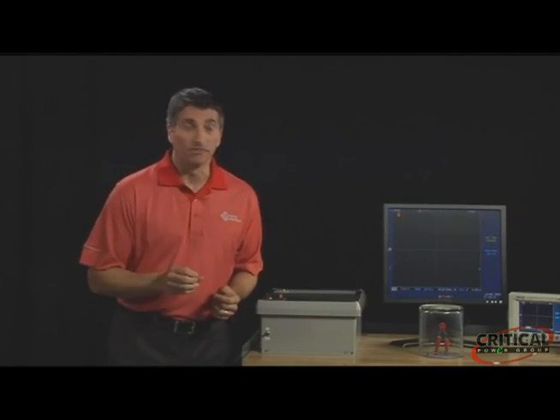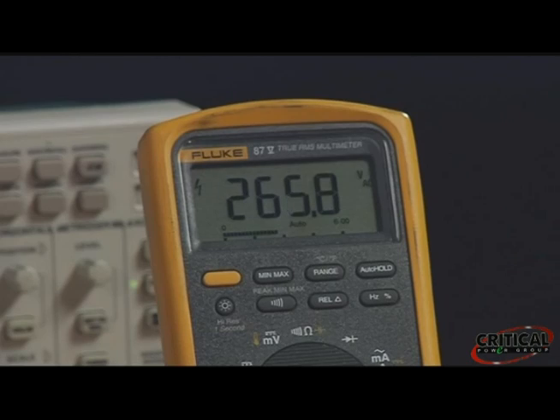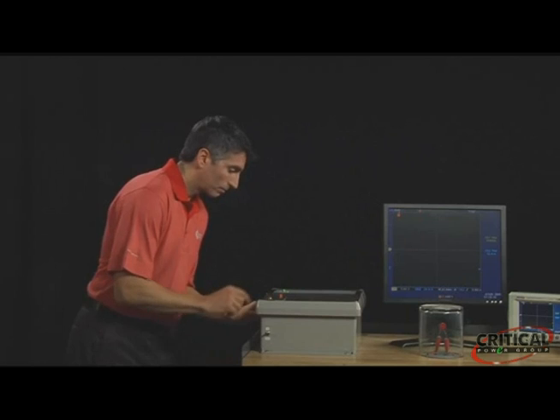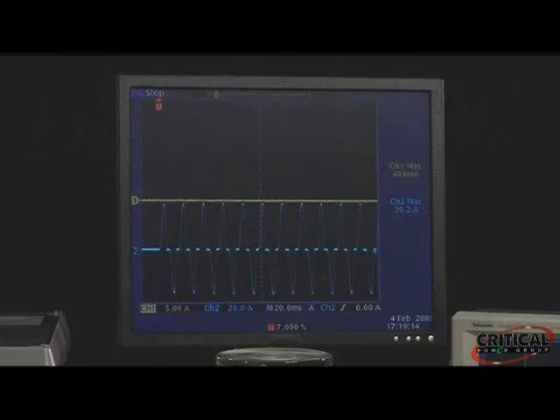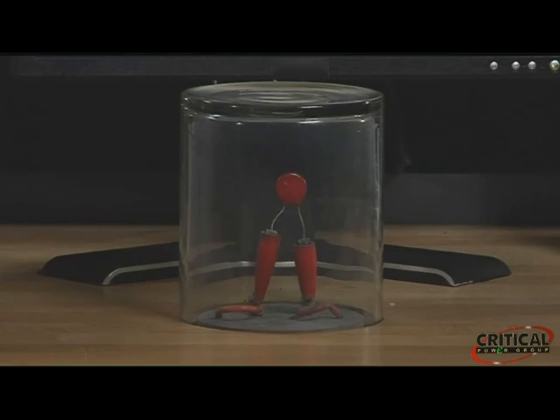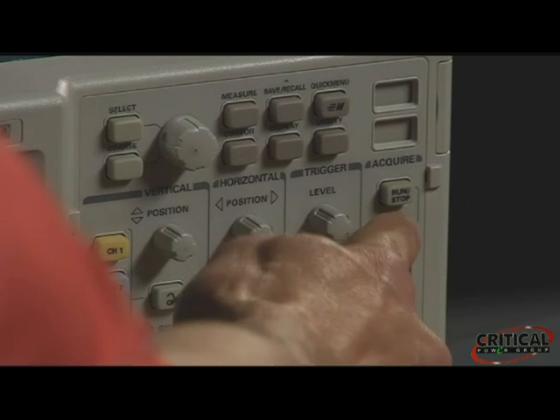We'll now increase the voltage to 270 volts. 270 volts is well past the voltage level that caused the MOV to fail. As you can see, the MOV is still intact and has very little current activity. The selenium cell had 39.2 amps flow through it and has continued to protect the MOV and the protected load during the TOV event. Now I'll reset the scope before the next test.